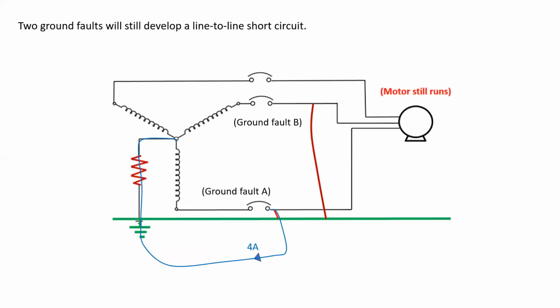Now, of course, we're still left with the possibility that if two ground faults were to develop, a line-to-line short circuit would then result. And of course, that would be bad, and we would have the same form of destructive force as what we saw in the solidly grounded low impedance system. But at least what we're doing here is reducing the risk to personnel with arc flash and blast. And if we're really quick and attentive, we can find the ground fault before there is a significant line-to-line short circuit.